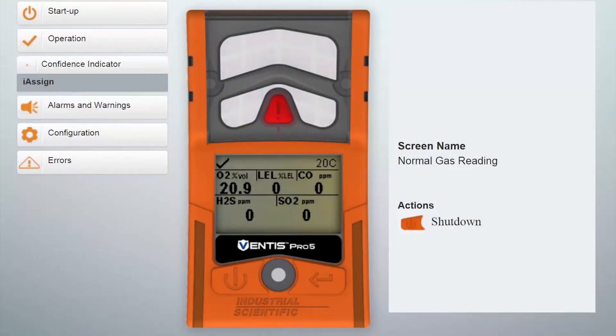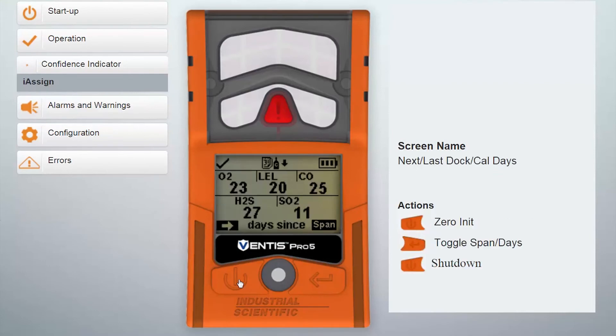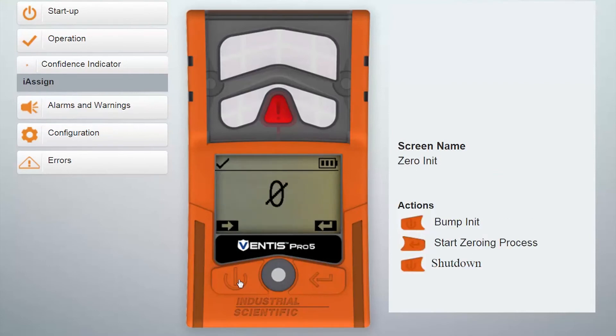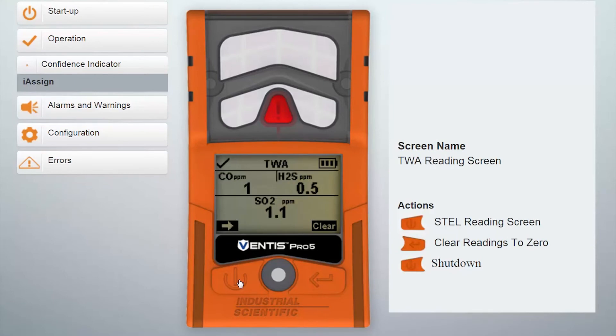The time-weighted average, or TWA screen, can also be enabled for the user to view those alarms in the Ventis Pro Series instrument. By going into the settings menu, you can enable that screen, and you can also set the level for the alarm. The time-weighted average, or TWA, is averaged over an eight-hour period, typically for a workday.